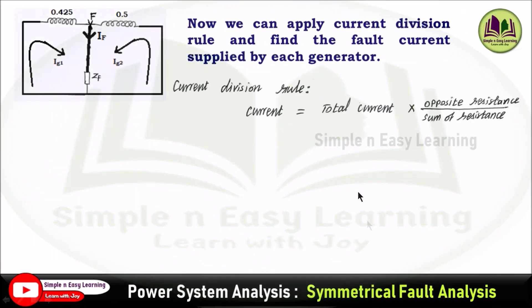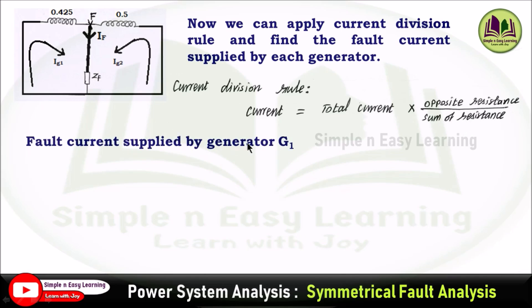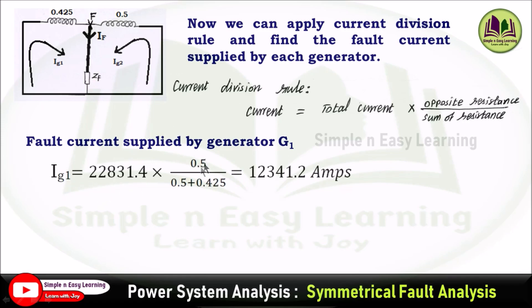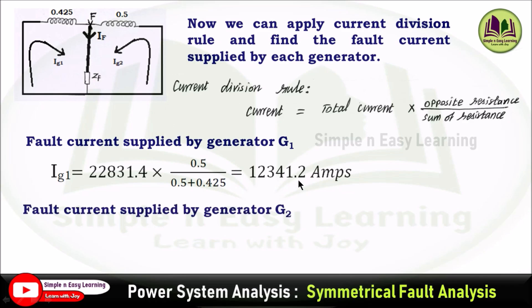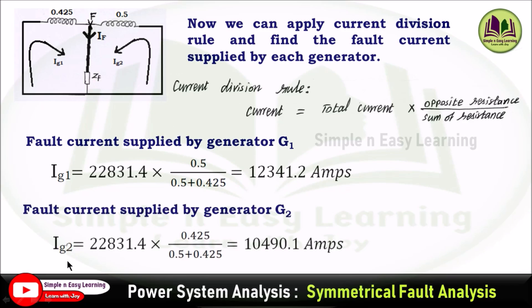Applying the current division rule — current = total current × (opposite impedance) / (sum of impedances). For generator 1, the opposite impedance is 0.5, so IG1 = total current × 0.5 / (0.5 + 0.425) = 12341.2 A. For generator 2, the opposite impedance is 0.425, so IG2 = total current × 0.425 / (0.5 + 0.425) = 10490.1 A. These are the fault currents supplied by each generator.